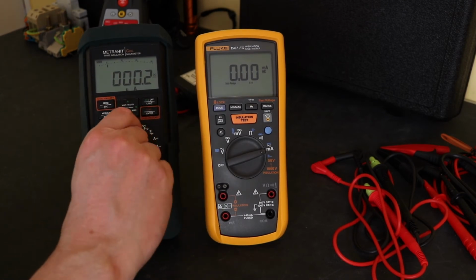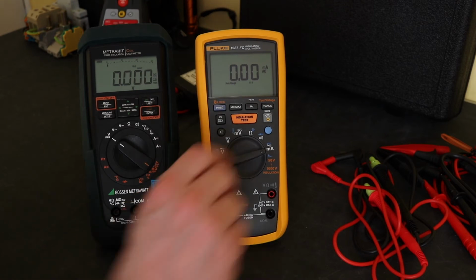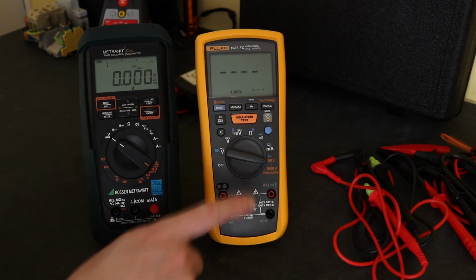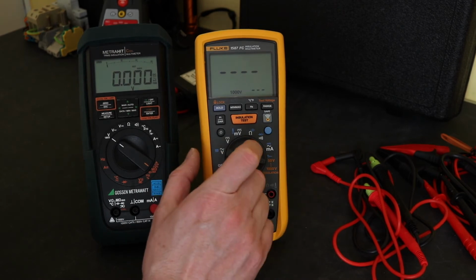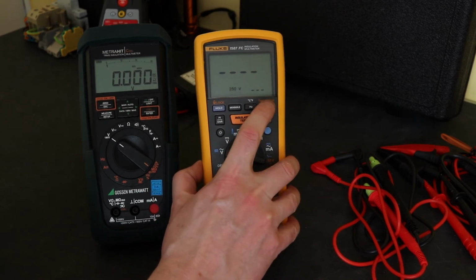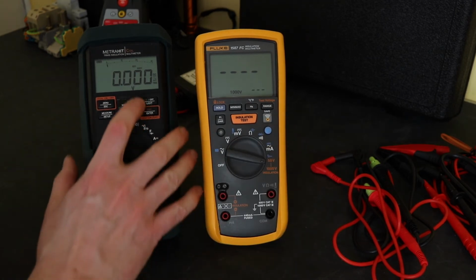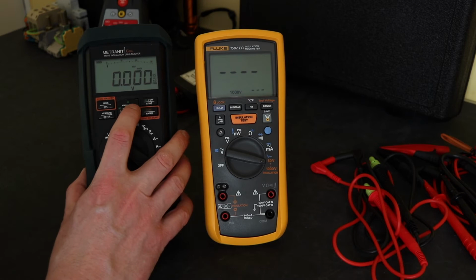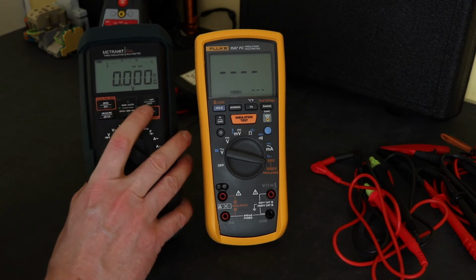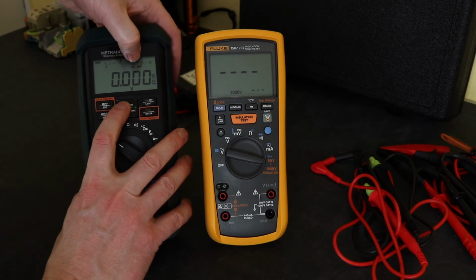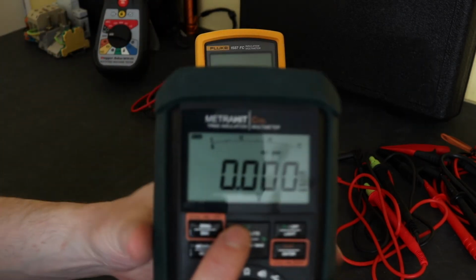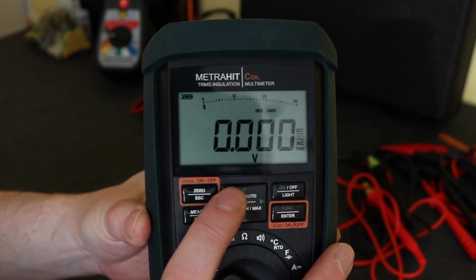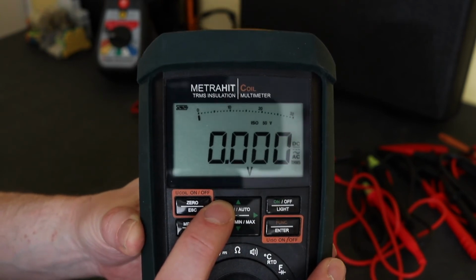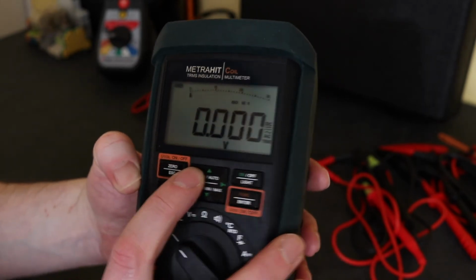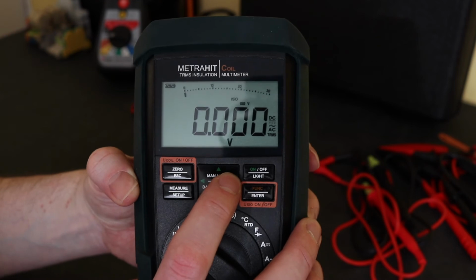Okay, flipping back, we go to the insulation test function. Just flip around here on the Fluke. Again, it warned me about the lead. Electronic selection of the test voltage there, 50 all up to 1000 volts through 5 ranges. You can also, not sure how well you'll see it on this one. It's very small. It's actually up here. I'll bring it closer, and hopefully you can see it operating there. And you can select the voltages there, 50. So same voltage selection.